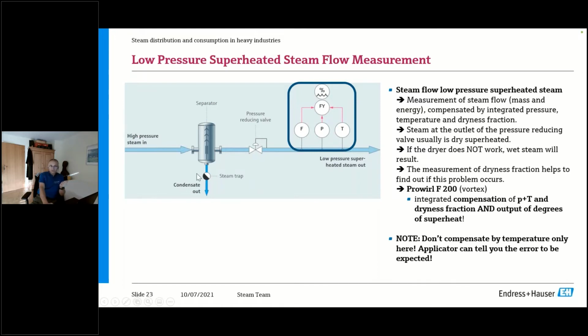If you don't have a separator, even worse. What happens then? You're sending, for instance, 90% dry steam into the pressure reducing valve. You're reducing that from a 10 bar pressure, 150 psi, down to a 3 bar pressure, 50 psi-ish. And what's happening? You increase the dryness fraction only slightly. You're coming from 90% to 92%. So it's an isenthalpic expansion that you're doing. So very important point. Please keep that in mind.